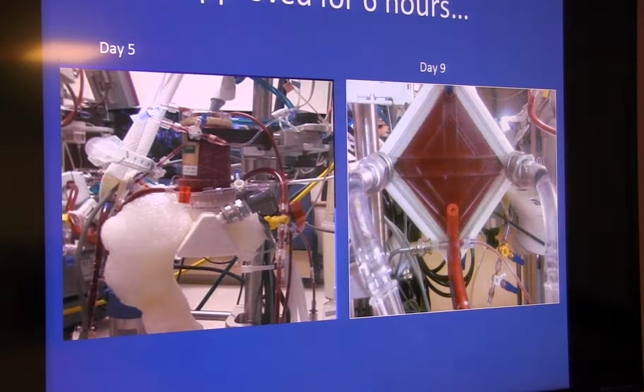Those two different ways that the oxygenator would fail usually happen at the same time. Even if you have a lot of clot in the oxygenator, it may still exchange gas. Right. That's what I was saying, with the old oxygenator we used to pay really close attention to the pre and post gases, because those would be the things that told us to change the old oxygenators. You'd come in one day and your PaO2 in your post oxygenator is now 240 and you're on 90% through the blender, and then you come in the next day and you hear that your post oxygenator PaO2 is 180 or 200 and you're on 100% through the blender. So now we know that oxygenator is on its way out.